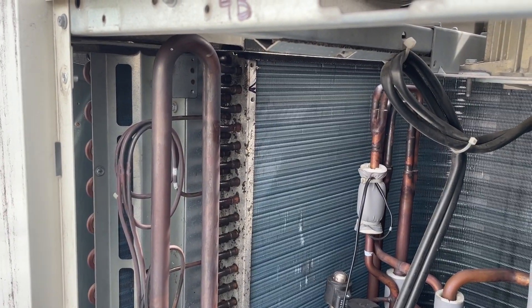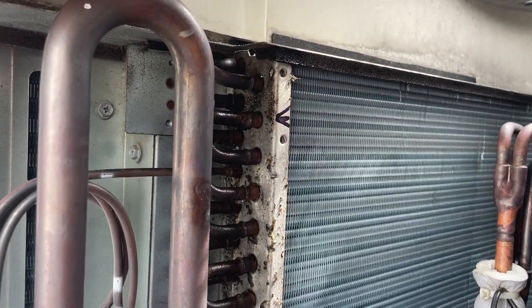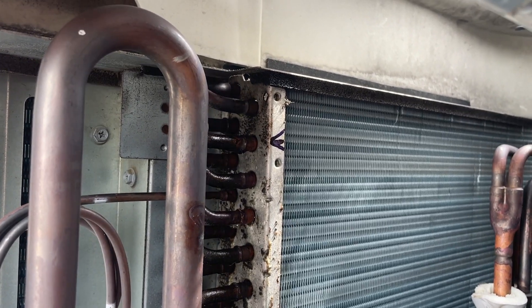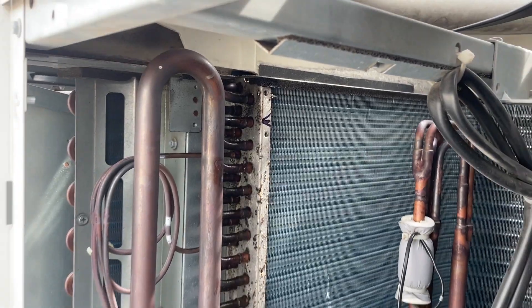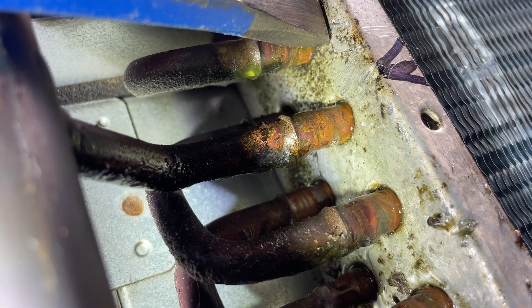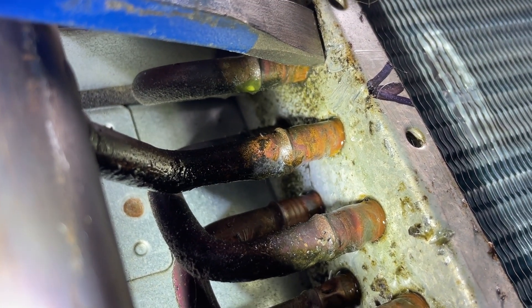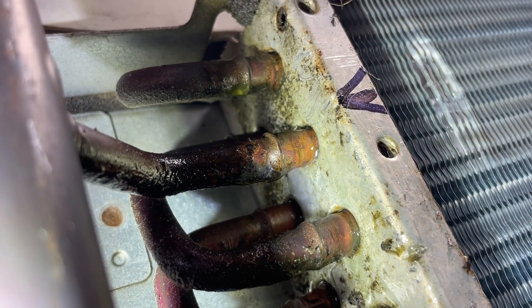Here's a look at where the leak's at, right where that black arrow is. It looks like it's coming out in a way that would indicate that the plate has rubbed through that U-bend — it is right there at the plate.